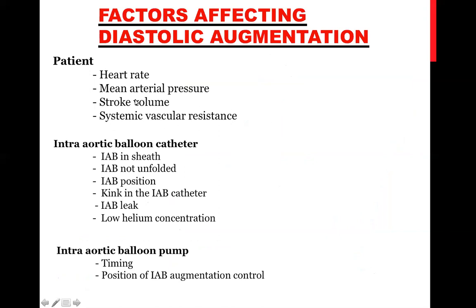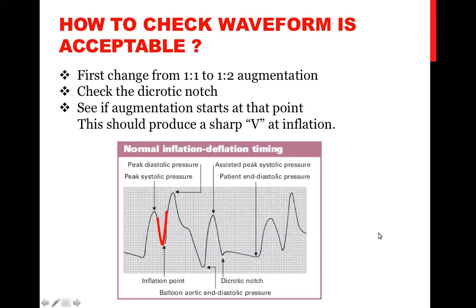So factors that affect augmentation include heart rate, mean arterial pressure, stroke volume, and systemic vascular resistance. All of those play into the variation of augmentation. Factors within the console itself or the balloon include the sheath, whether the balloon is unfolded, if there is a kink, if there is a leak in the gas, and if there is low helium concentration.